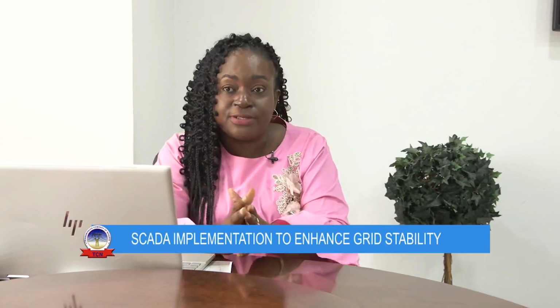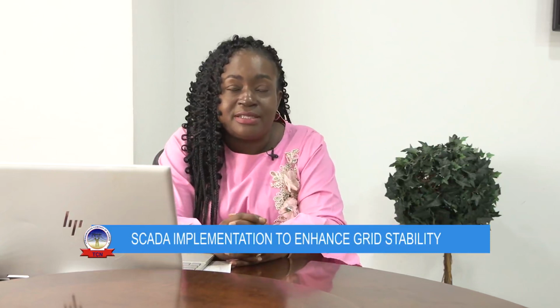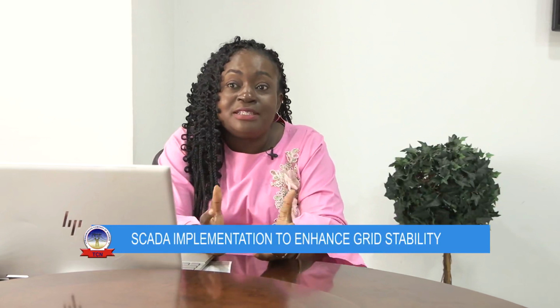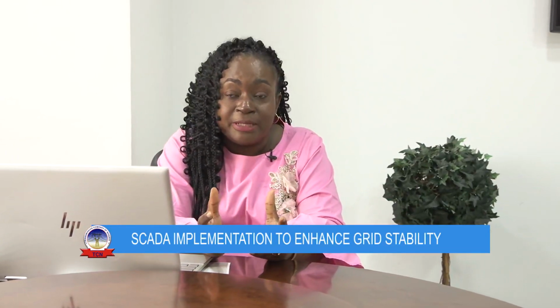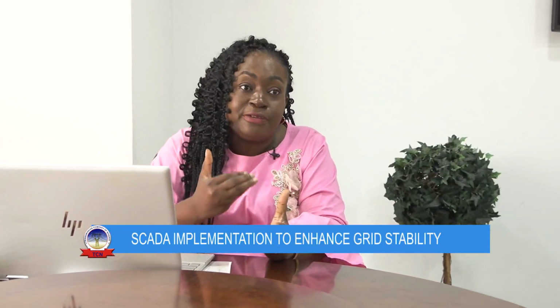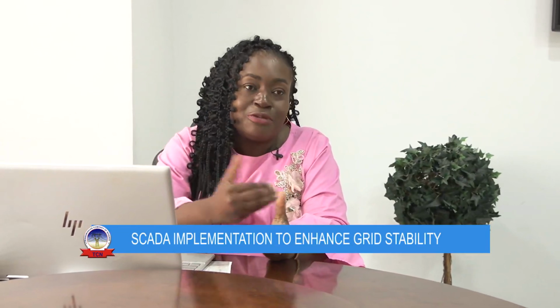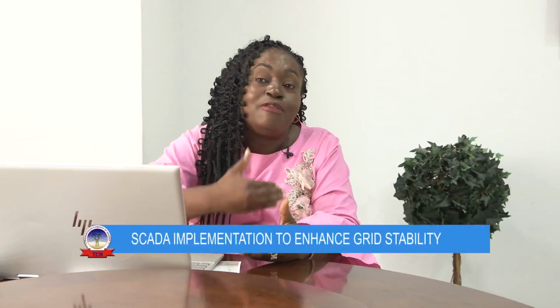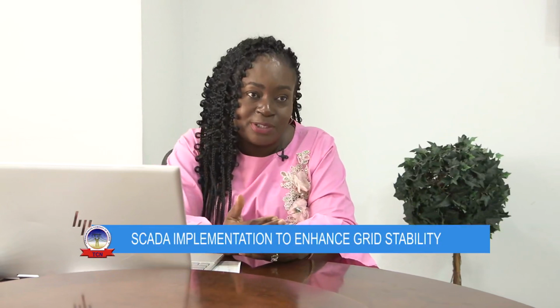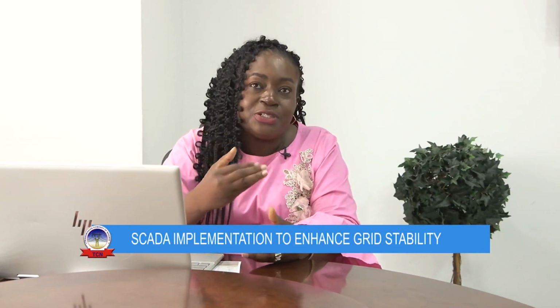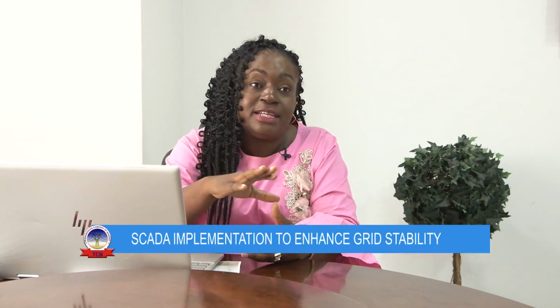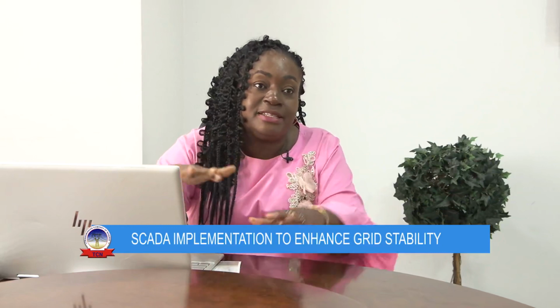There's a problem coming, before it gets to the point where there should be a reaction. So the system operator at the National Control Center sees it and says, I'm getting this information that there's a potential problem, and he's getting enough information to take action. Like if you're sitting down and suddenly feel pain, you know you have to do something about it, maybe take paracetamol, because over time that's what you've been told. All this information is programmed into the SCADA system so there is a reaction anytime there's a system imbalance.